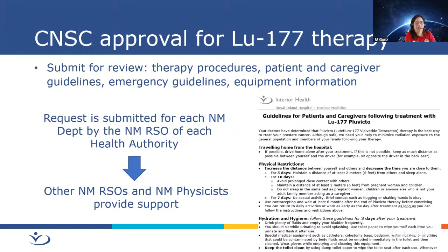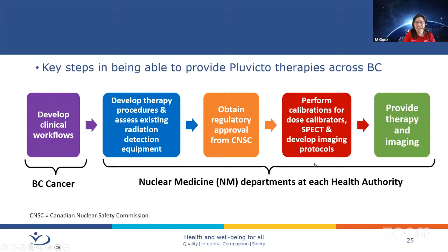So now the last few things that we needed to do was do calibrations for a few other equipment, like I mentioned. So dose calibrators that we're going to use to actually measure the activity to patient, the SPECT cameras, and to develop the actual imaging protocols, what we're actually going to use to image the patients. So dose calibrators are really, really important because they're the ones that measure the activity that you're actually going to give to your patients. And none of those departments had ever used lutetium before. So we had to make sure that their dose calibrators were appropriately calibrated for lutetium.